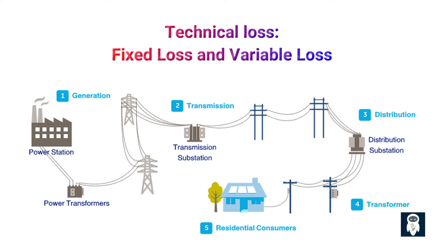Technical loss can be further divided into two categories: fixed loss and variable loss. Fixed loss is the loss of energy that does not depend on the current or the load, but on the voltage and the duration of the energization. Fixed loss occurs mainly in transformers, measuring devices, and control devices.